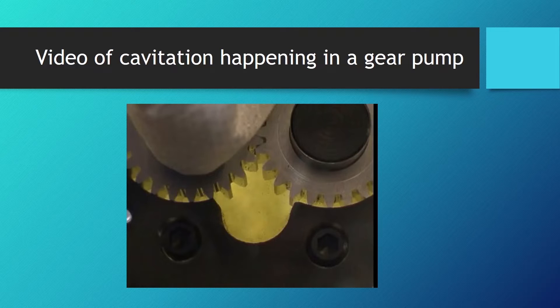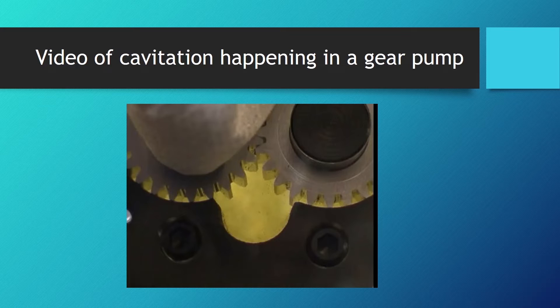Ways to know if you have cavitation happening in your system include the sound — it has a very specific sound of debris rolling around in your pump, like having tiny rocks just tumbling around in your system. Another sign is actual physical evidence. As part of your general maintenance you should be inspecting and replacing the hydraulic oil filter elements at regular intervals based on the duty cycle and how often the application is used. If during inspection you find metallic debris in the filter, it could be a sign that you're experiencing cavitation in the pump.